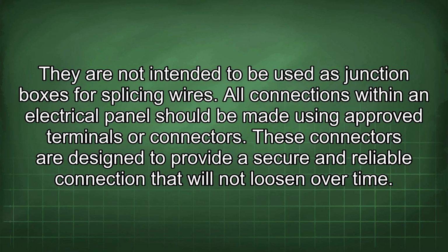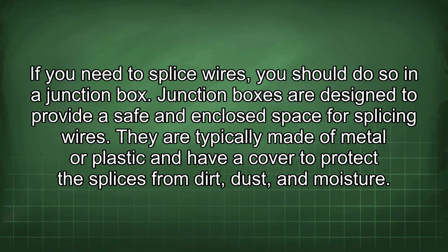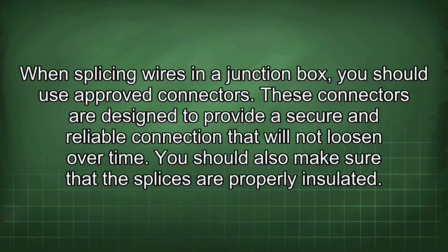All connections within an electrical panel should be made using approved terminals or connectors. These connectors are designed to provide a secure and reliable connection that will not loosen over time. If you need to splice wires, you should do so in a junction box. Junction boxes are designed to provide a safe and enclosed space for splicing wires. They are typically made of metal or plastic and have a cover to protect the splices from dirt, dust, and moisture. When splicing wires in a junction box, you should use approved connectors.